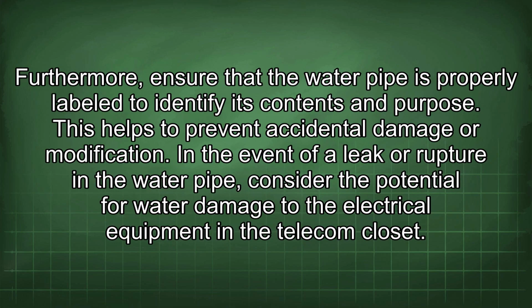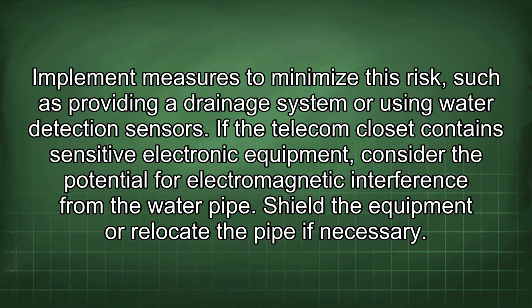Furthermore, ensure that the water pipe is properly labeled to identify its contents and purpose. This helps to prevent accidental damage or modification. In the event of a leak or rupture in the water pipe, consider the potential for water damage to the electrical equipment in the telecom closet. Implement measures to minimize this risk, such as providing a drainage system or using water detection sensors. If the telecom closet contains sensitive electronic equipment, consider the potential for electromagnetic interference from the water pipe. Shield the equipment or relocate the pipe if necessary.